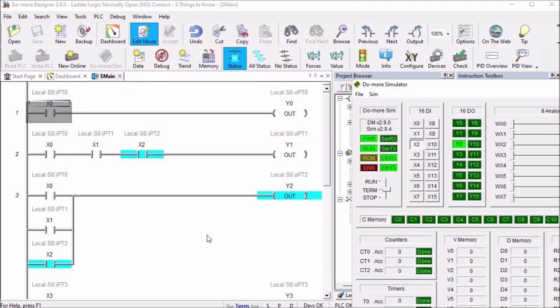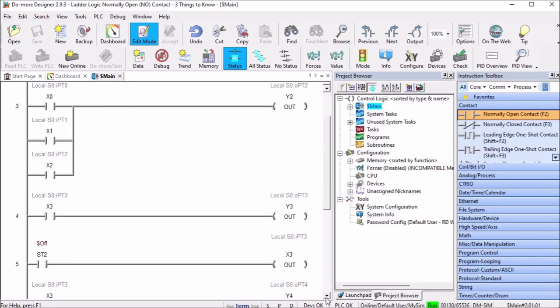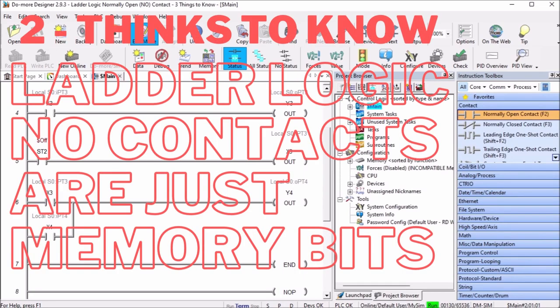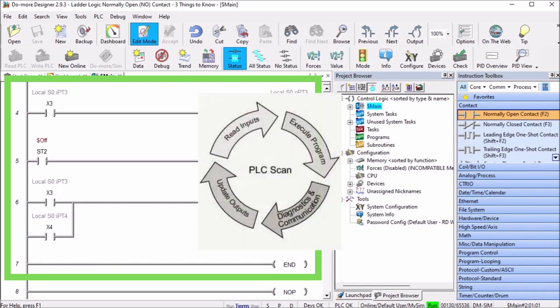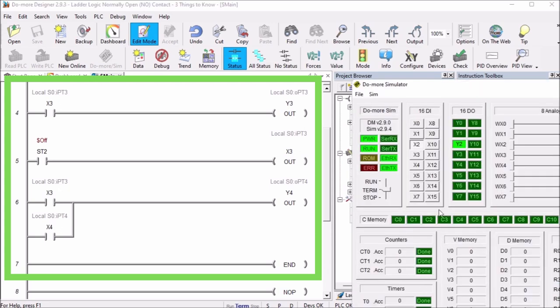Next, the second thing we will talk about is the ladder logic normally open contact is just a memory bit. The normally open contact input on the ladder logic is just a memory bit within the PLC. A cyclic scan of the PLC consists of reading the input, solving logic, diagnostic and communication, setting the outputs. During that scan, we read the inputs and transfer that information to an internal memory bit. This means the ladder logic can manipulate its value. Take a look at the next example that we have, and again I will call up our simulator.